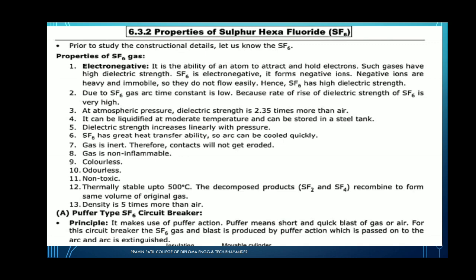Due to SF6 gas, the arc time constant is low, because the rate of rise of dielectric strength of SF6 is very high. Next property: at atmospheric pressure, the dielectric strength is 2.35 times more than air. This is the property of SF6, sulfur hexafluoride gas. Next property: it can be liquefied at moderate temperature and can be stored in a steel tank. Next property: dielectric strength increases linearly with the pressure.